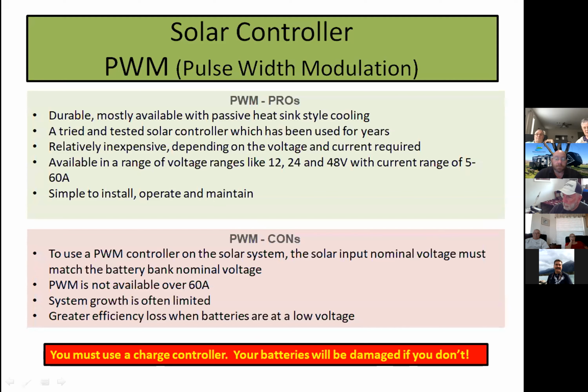The oldest version that's been around for many years is called a pulse width modulation, or PWM, solar controller. PWMs are very cheap but not very efficient. They've been around a long time and are very inexpensive—available in a range of voltages like 12, 24, or 48 volts, with current ranges of 5 to 60 amps. They're simple to maintain: you mount it up, put your fuse in the line, and run the wires into the controller. It's good to go. There is a lot of efficiency loss when the batteries are at a low voltage.